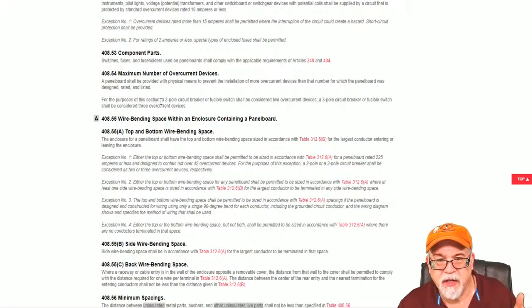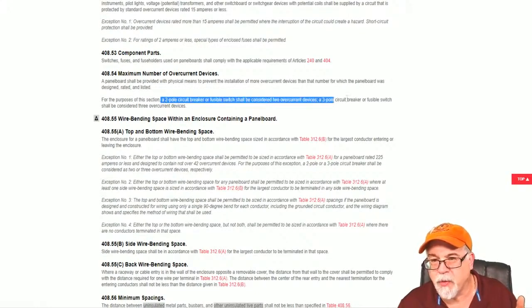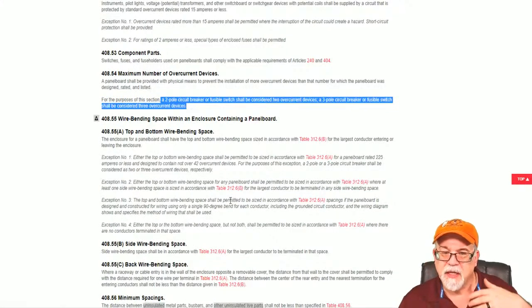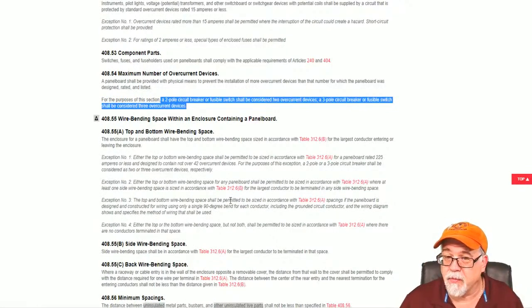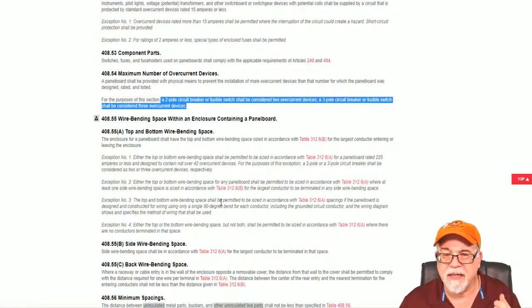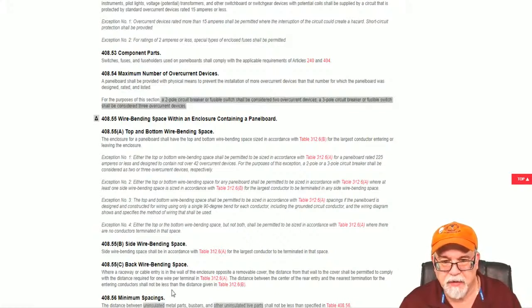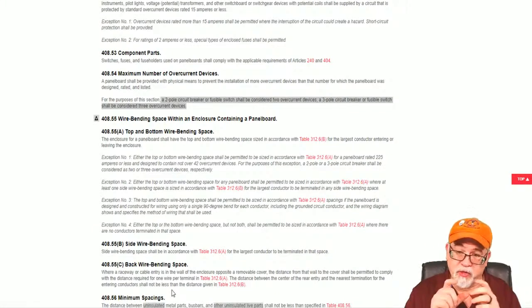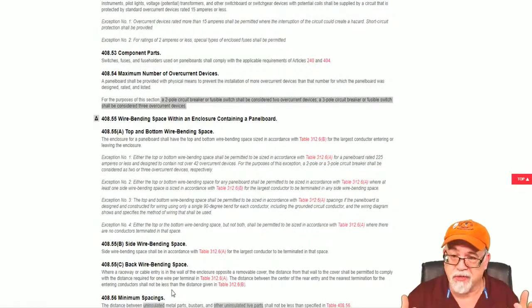For the purpose of this section, a 2-pole circuit breaker or fuse shall be considered 2 overcurrent devices. A 3-pole circuit breaker shall be considered 3 overcurrent devices. That comes up a lot when people say, what do I consider a 2-pole breaker? It's 2 overcurrent devices, or a 3-pole breaker, it's 3 overcurrent devices. I get that question quite a bit when it comes to what is a 2, what is 3, and obviously a single one counts as 1.